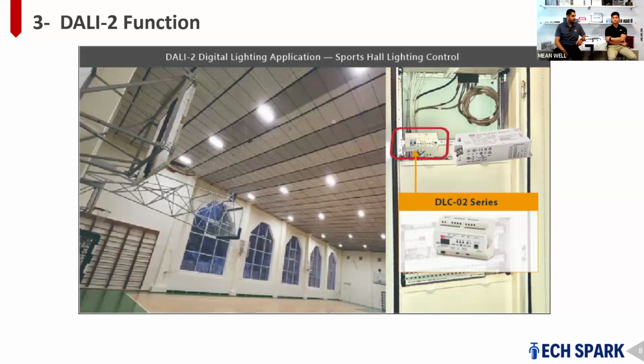That DALI feature was only for our DALI DLC dash 02. As I mentioned, it can cover up to 128 drivers using two buses. Bus number one can connect up to 64 drivers, and those drivers can be communicated with using just 2 wires. With 4 wires total, you're able to communicate and control 128 drivers. But with 3-in-1, it has 2 cables, and each 2-cable set has to be connected to the driver. So if you have 100 units of 3-in-1, you'd have to connect 200 wires. Compare that to just 4 wires with DALI.